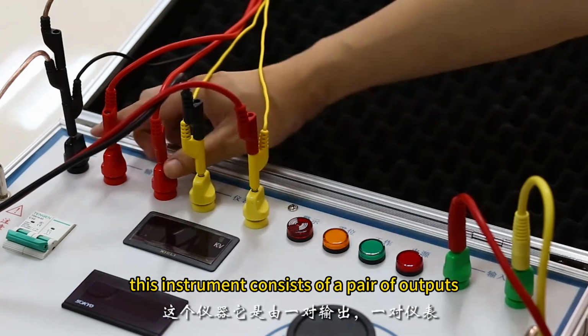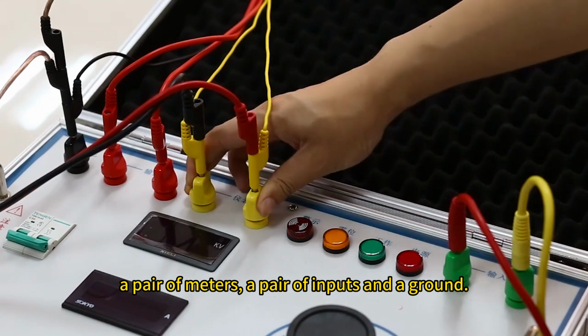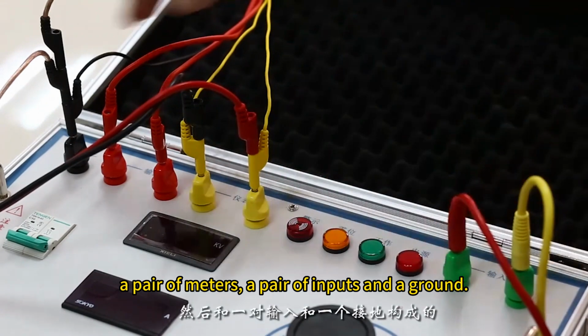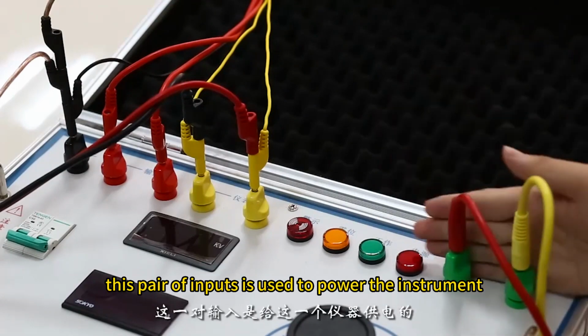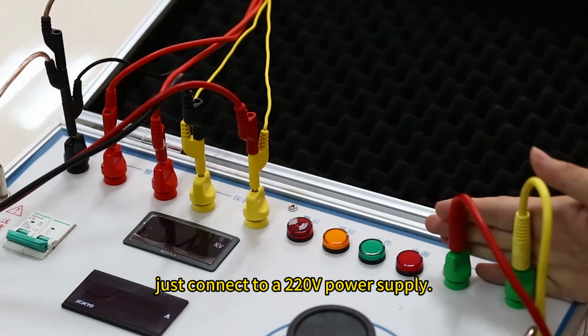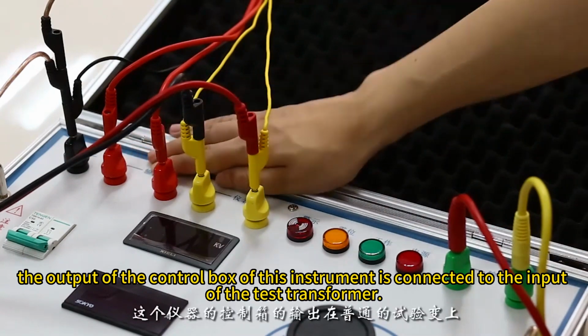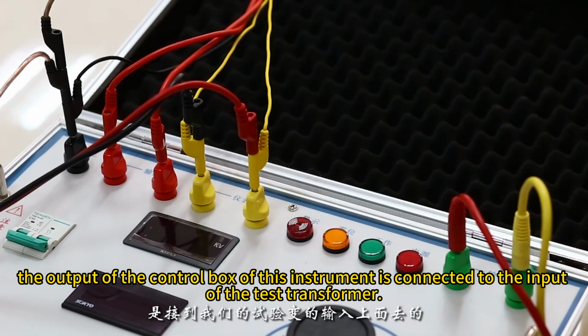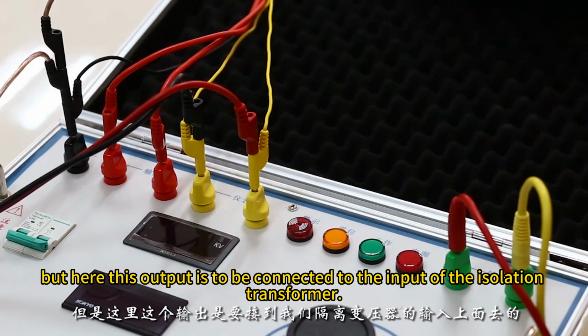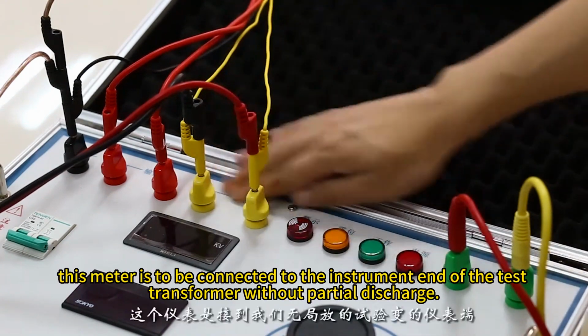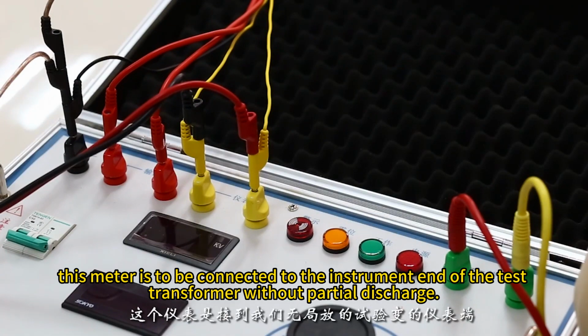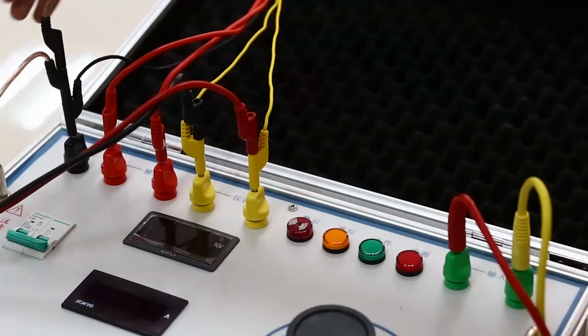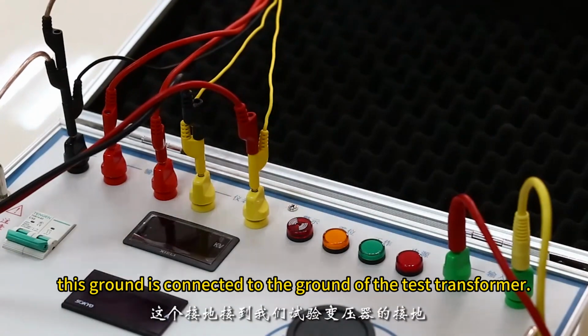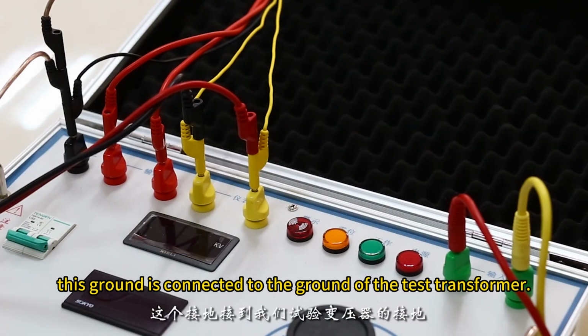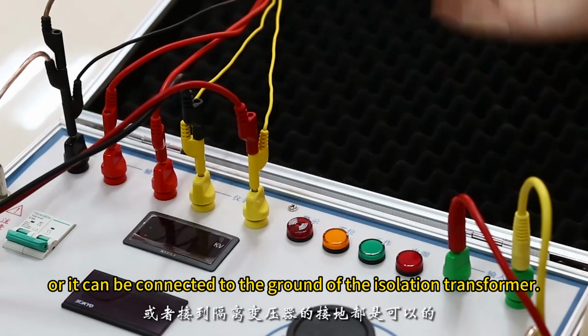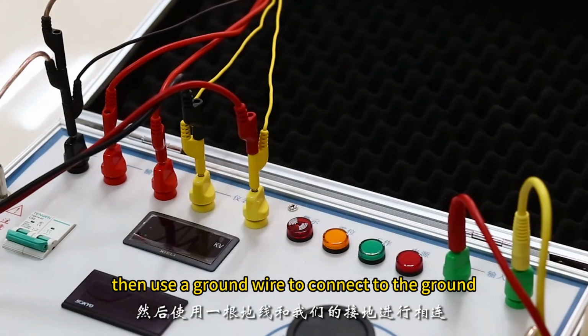This instrument consists of a pair of outputs, a pair of meters, a pair of inputs, and a ground. This pair of inputs is used to power the instrument. Just connect to a 220 volts power supply. The output of the control box of this instrument is connected to the input of the test transformer. But here, this output is to be connected to the input of the isolation transformer. This meter is to be connected to the instrument end of the test transformer without partial discharge. This ground is connected to the ground of the test transformer. Or it can be connected to the ground of the isolation transformer. Then use a ground wire to connect to the ground.